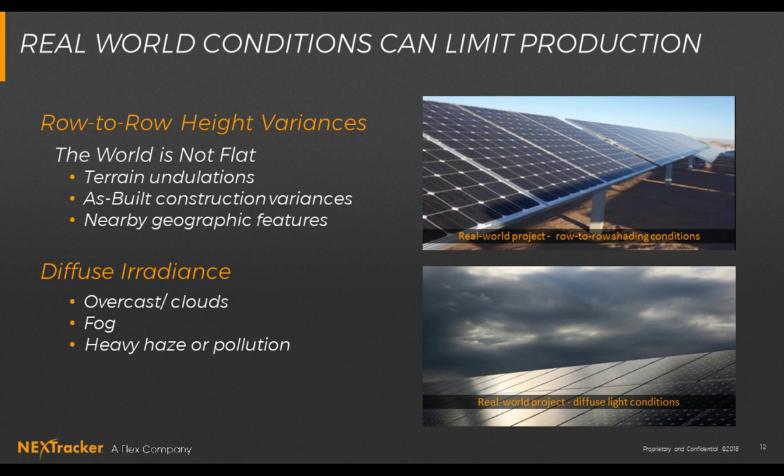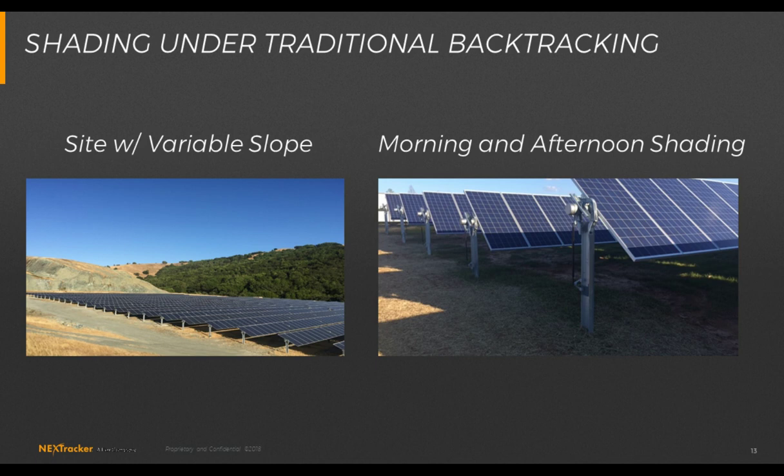And as we spoke earlier, in cloudy conditions, there's an enormous opportunity to increase the power. Like if it's late afternoon or early morning and it's really cloudy, but the angle of the sun is perpendicular to the panels, if you rotate back closer to horizontal, you'll see an absolute increase in the amount of power in those conditions by very large numbers, like 10 to 12 to 15% on the overall system. So this is the opportunity. Venkata is going to go through now and speak to how we get it done.